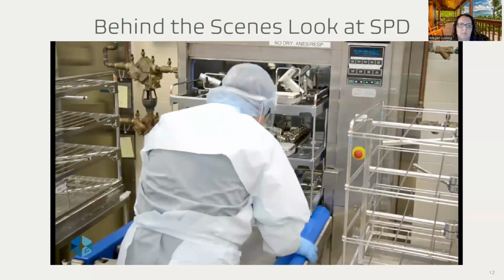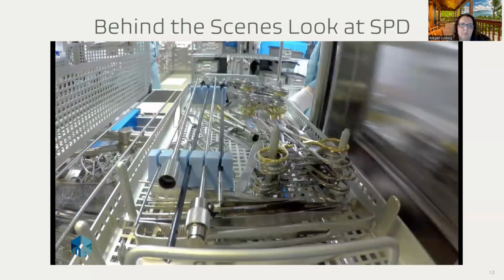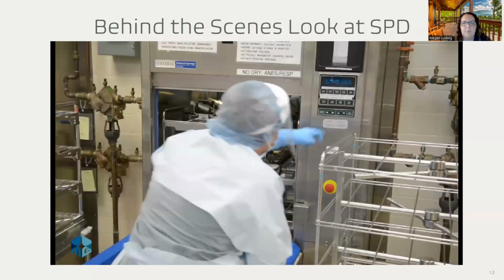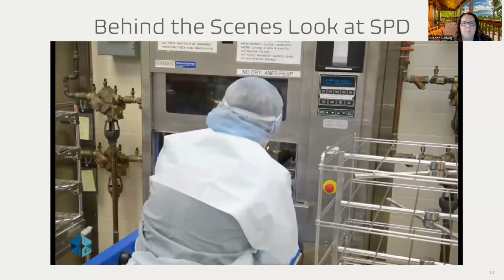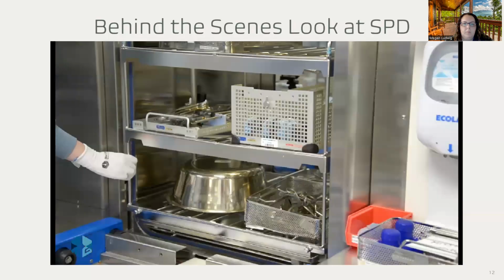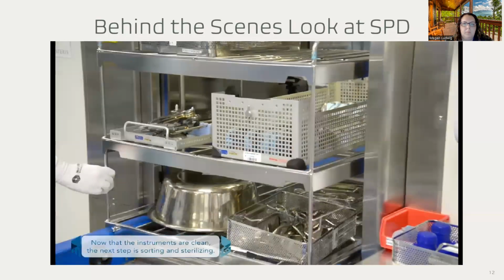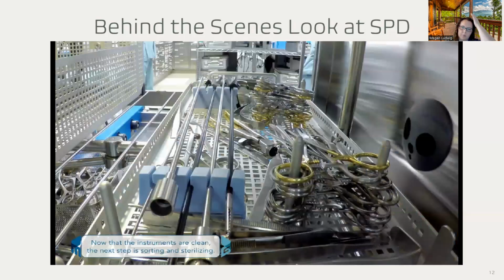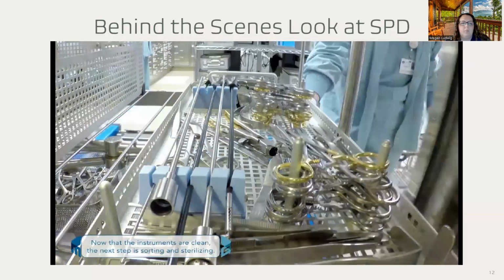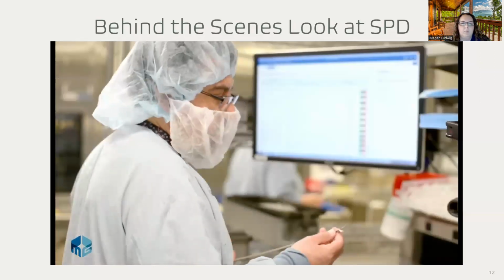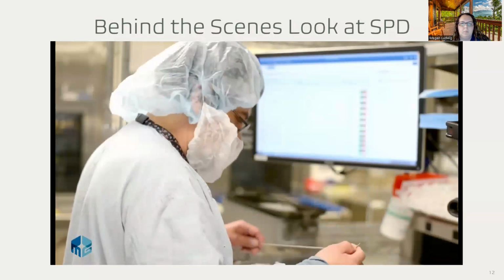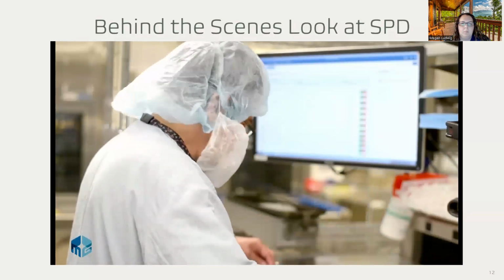Mechanical cleaning is done in a washer disinfector similar to a high-powered dishwasher. This step removes anything that might be left on the instruments. The washer rack has spray arms that spin and clean the instruments using detergents and high-pressured spraying water. Each cycle provides a thermal disinfection so the instruments are safe to handle. When the cycle is complete, we can now inspect and assemble the instruments in preparation for sterilization.